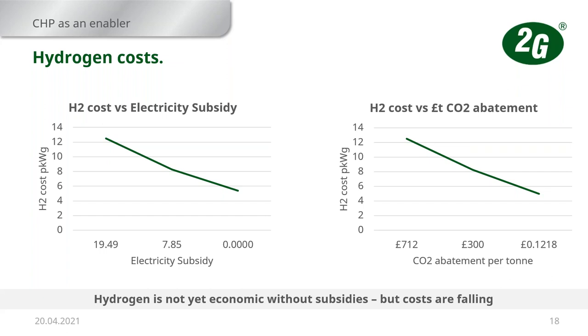Yeah, I guess that question was driven by what you said earlier about the difference in calorific value. Yeah, no, as I said, even though we get a derate running hydrogen, specifically because we don't want to get the knocking issues on the engine causing it to shake itself to death, once we've derated the engine, or once we know we want to run that derated value on natural gas, we just have the injection of the natural gas going up to that same value. We don't overpower the engine again.